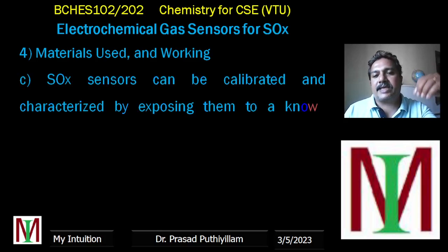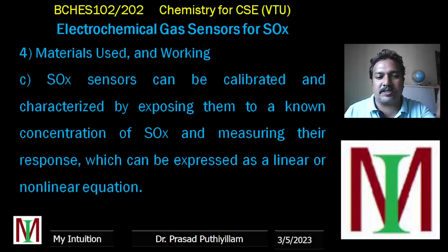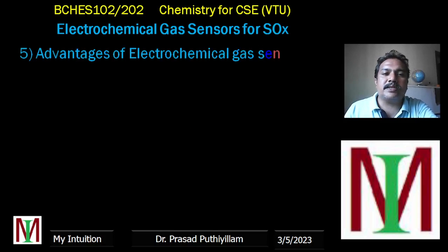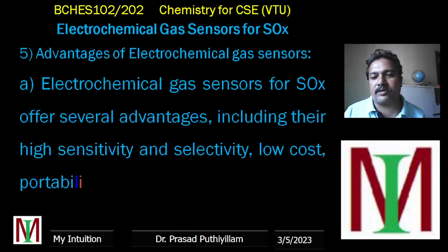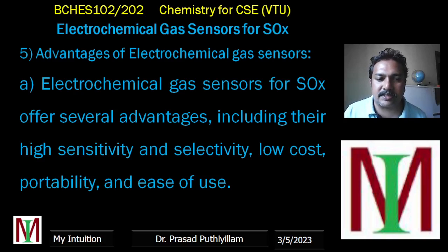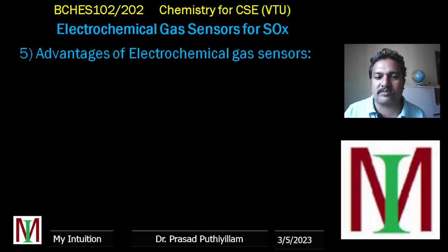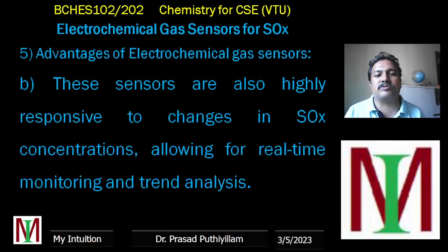The SOX sensor can be calibrated by exposing it to known concentrations of SOX and measuring its response, which can be expressed as a linear or non-linear equation. Advantages of electrochemical gas sensors for SOX include high sensitivity, high selectivity, low cost, portability, and ease of use.